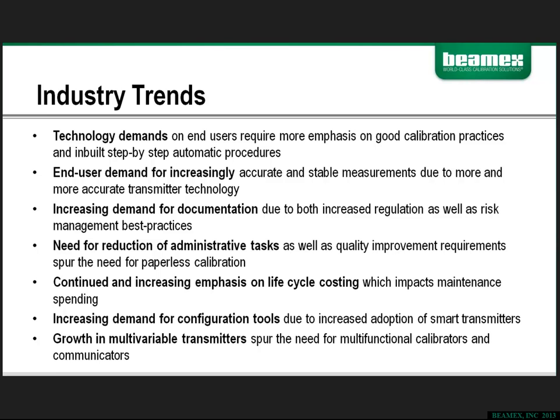Increased levels of regulation and risk management practices have led to an increased demand for documentation. Administrative tasks continue to increase this, reducing the amount of time that the technical staff has to perform calibrations and maintenance in the facility. Paperless calibration was developed to meet this specific need. The cost of maintenance continues to be a hot-button issue in this industry. As a result, there's a lot more emphasis being placed on life cycles for instrumentation.